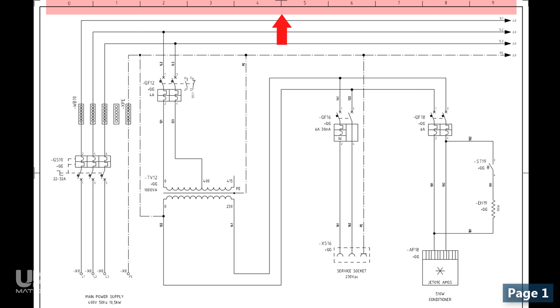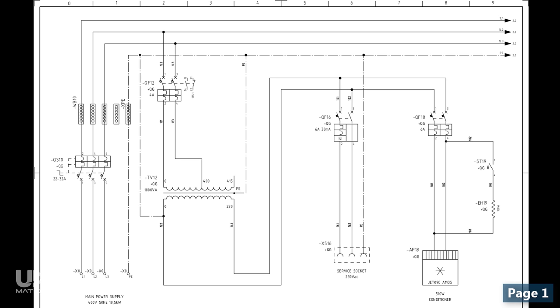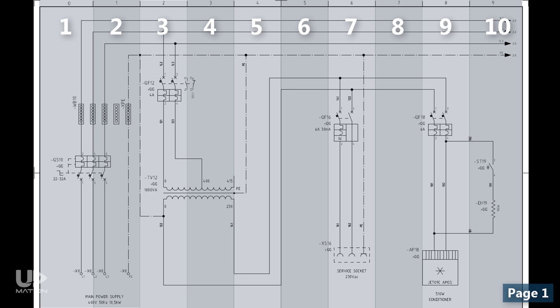You've also noticed the grounding chassis and its branches where it is needed. Before we continue to the next page, you may ask what these numbers on top of the page are. This is a very good question. Actually, these are the column numbers and they have divided each page of this drawing to 10 columns. As you see, there are some devices in each column and we can use these column numbers in combination with the page number to address different devices, contacts, terminal blocks and so on in other pages.